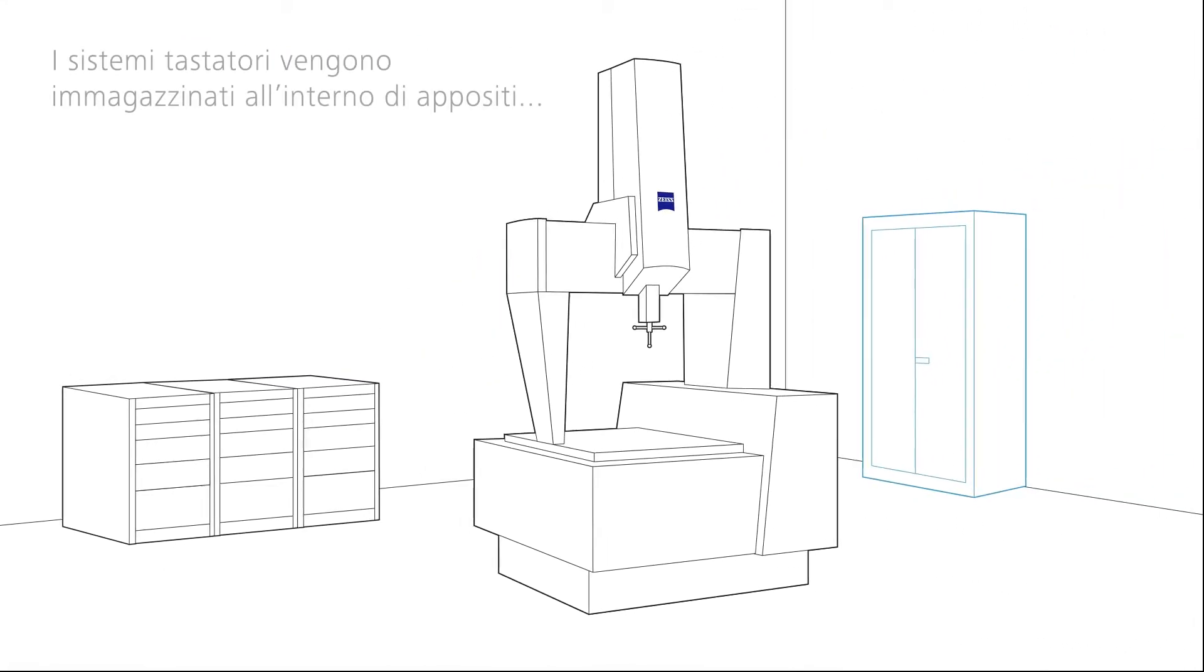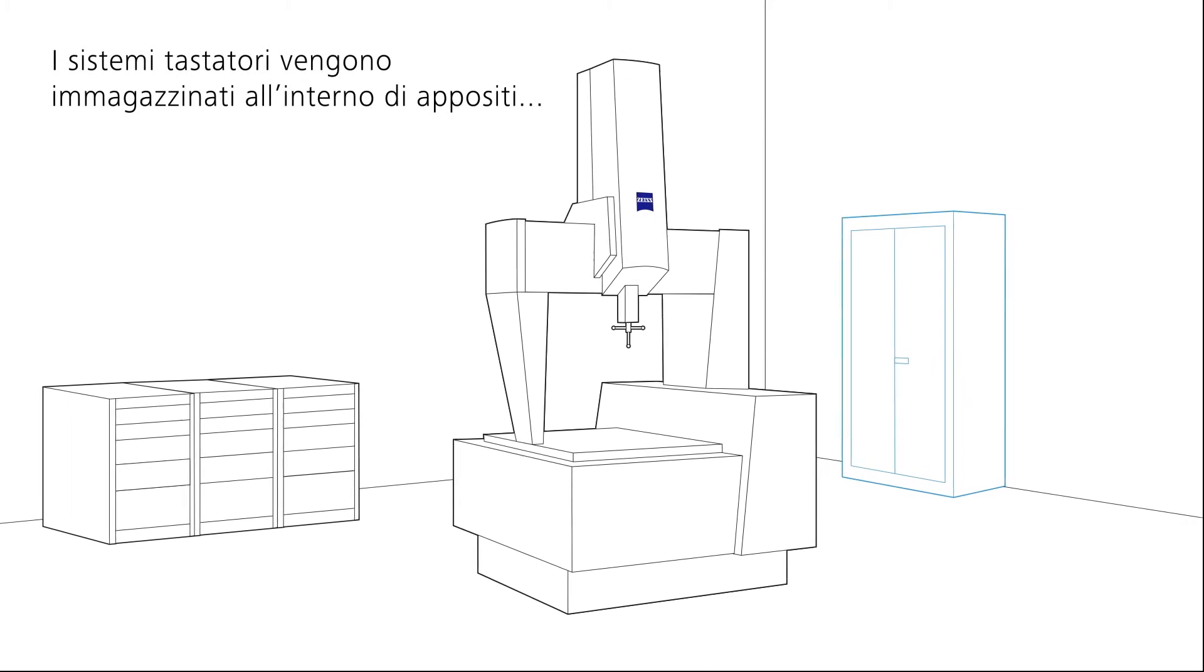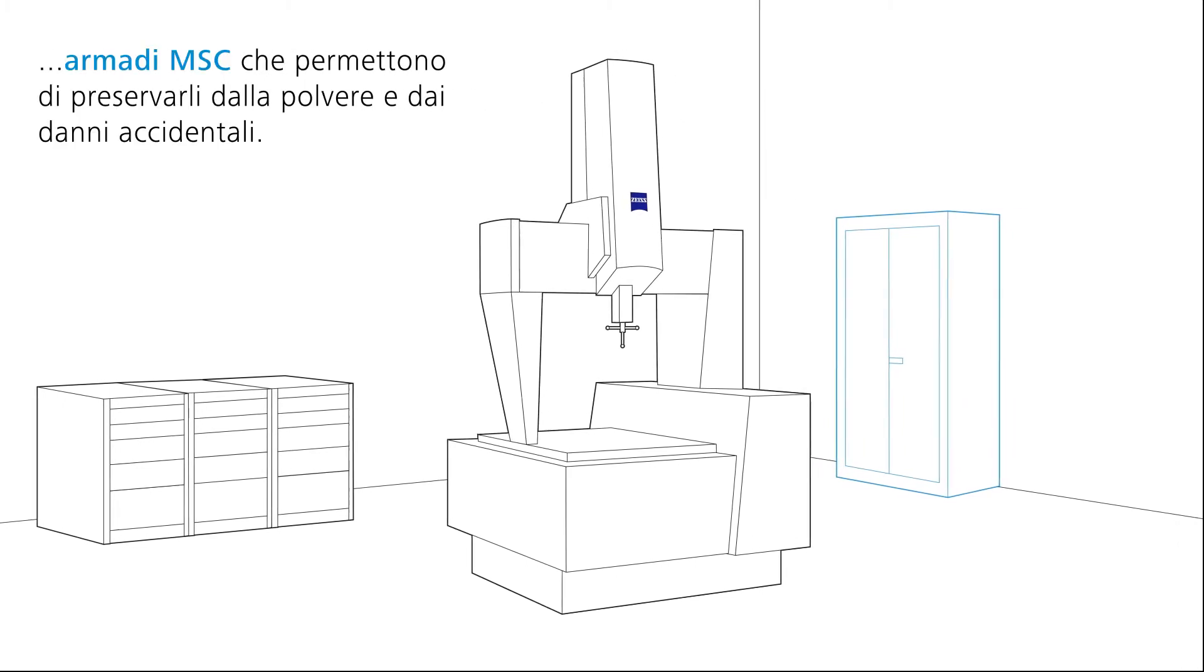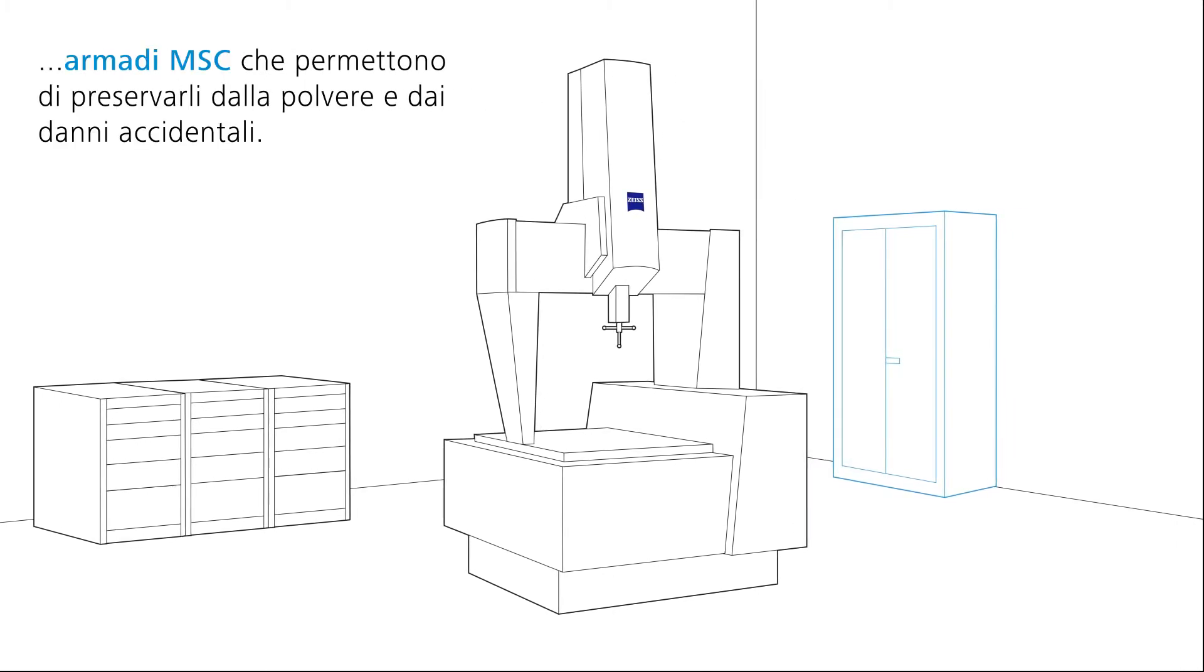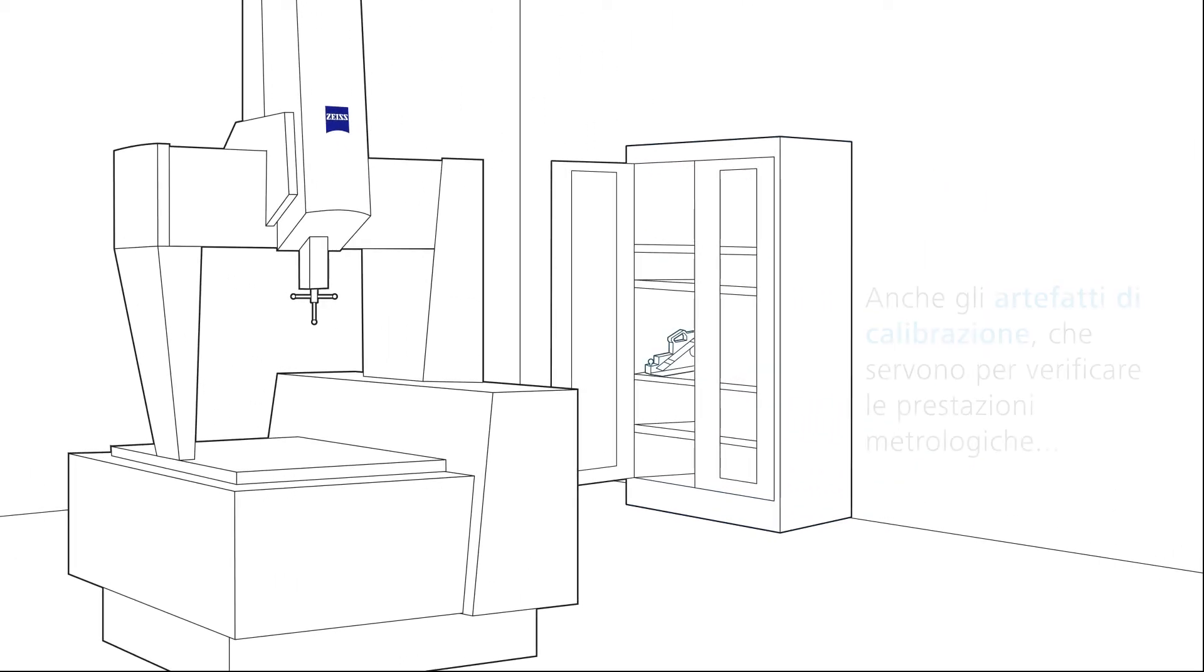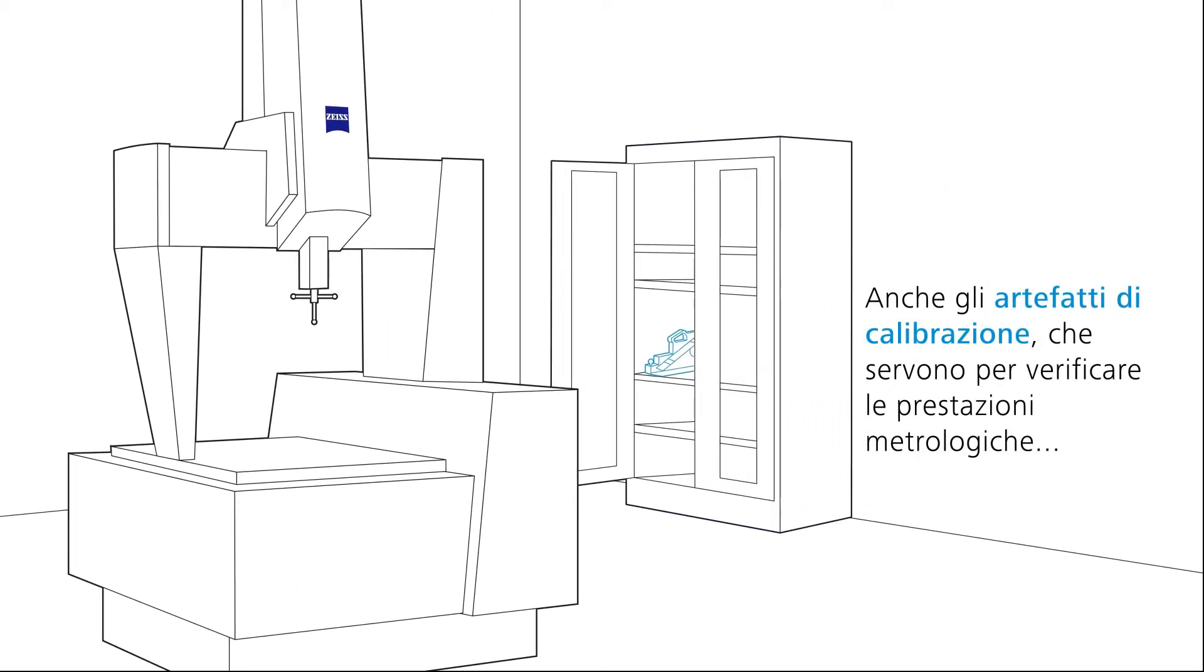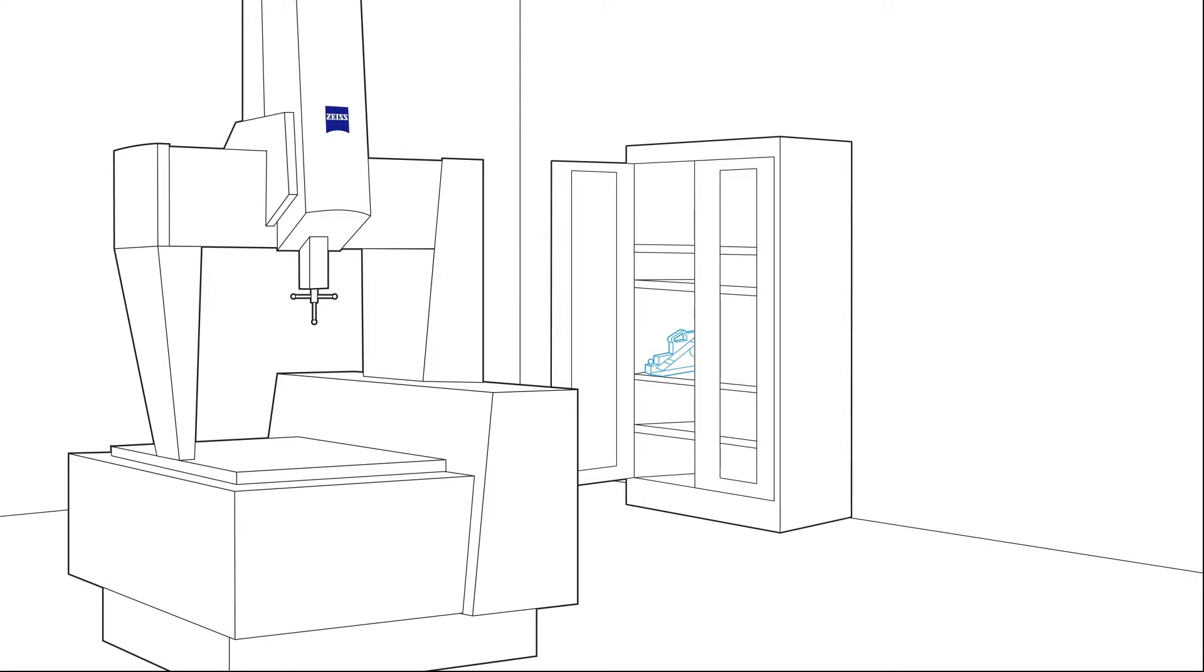The high quality stylus systems are optimally stored in a dust and access protected cabinet. The calibration artifacts used to check the precision of the CMM at regular intervals are also kept there.